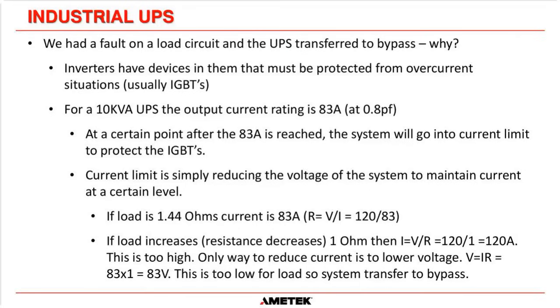So to stay at 83 amps, we would have to lower the voltage. V equals IR once again. So it's 83 times 1, which is 83 volts. That means we would have to lower the output of the UPS to 83 volts to keep the load at 83 amps. And that's too low for your load systems.